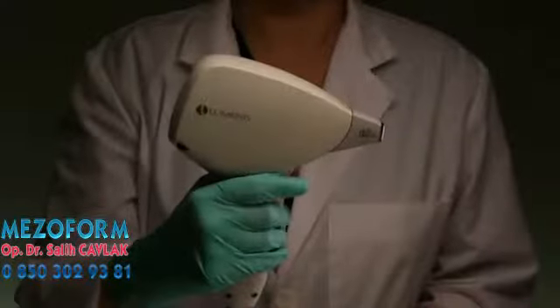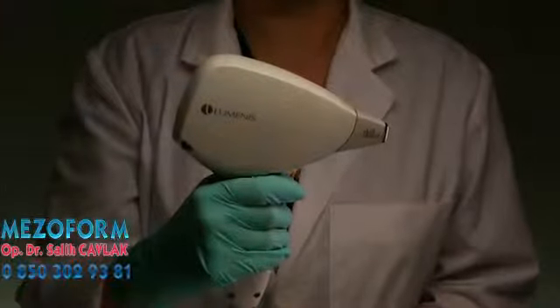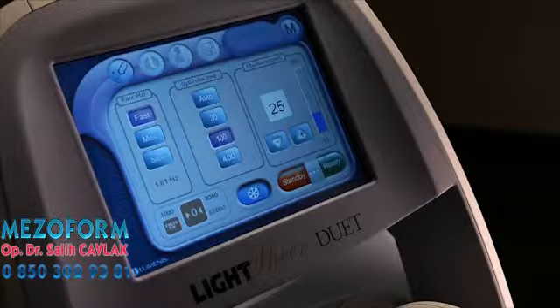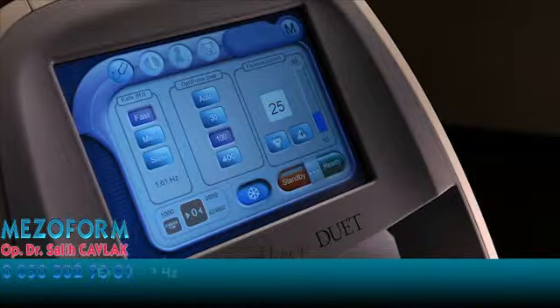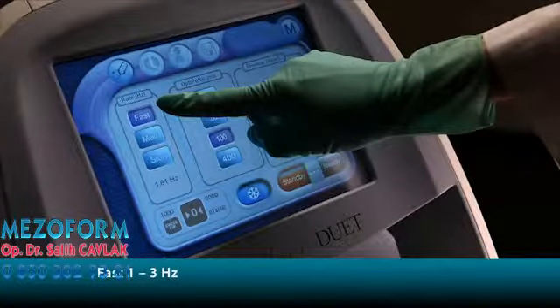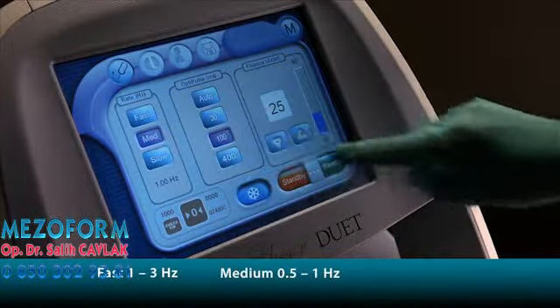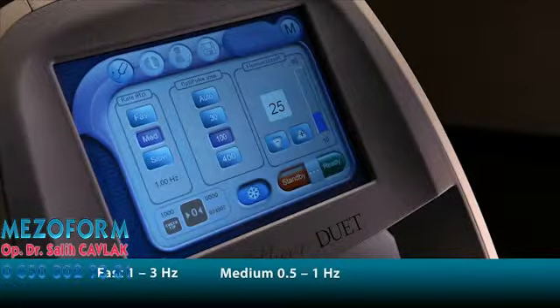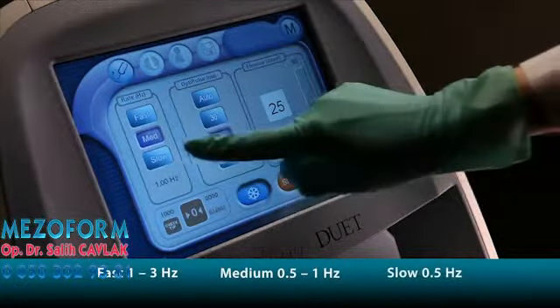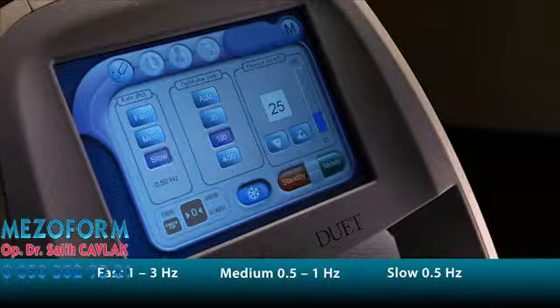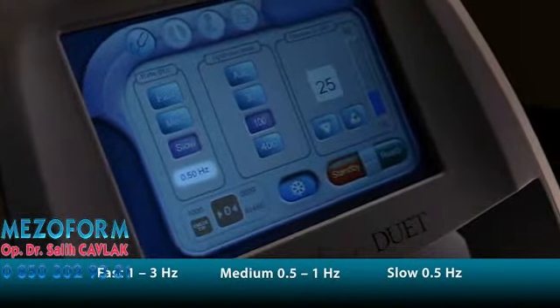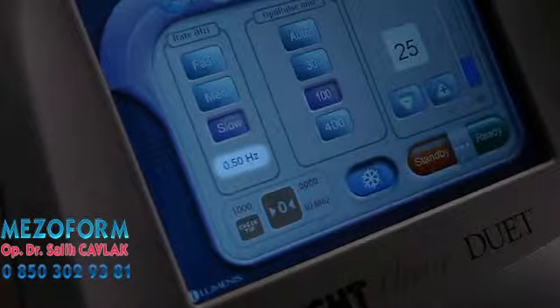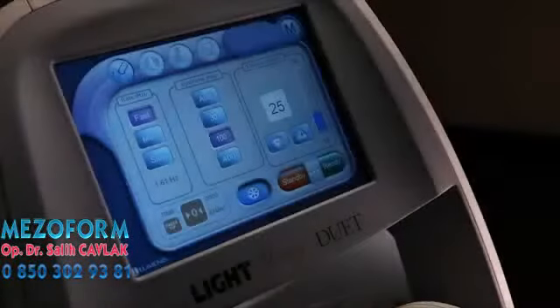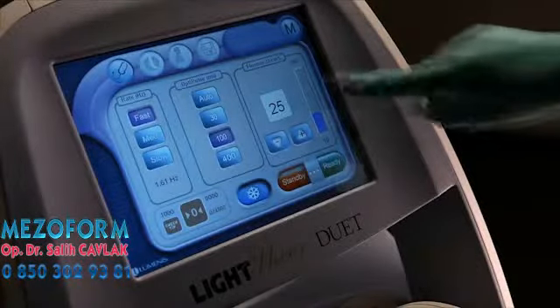With the handpiece enabled and the trigger held in the depressed mode, the rate at which pulses repeat can be adjusted from fast at 1 to 3 Hz to medium 0.5 to 1.0 Hz to slow, which is 0.5 Hz. The actual rate is determined by the pulse duration and fluence and is displayed at the bottom of the rate column. OptiPulse has 4 user-selected modes.